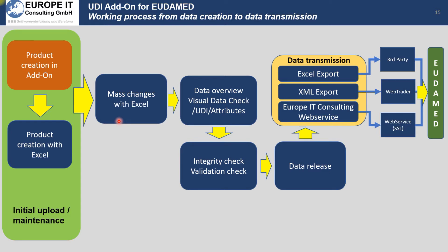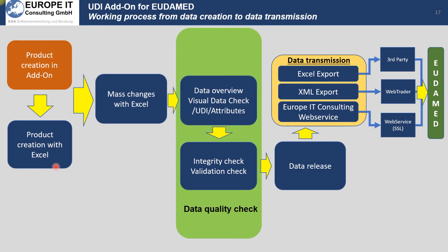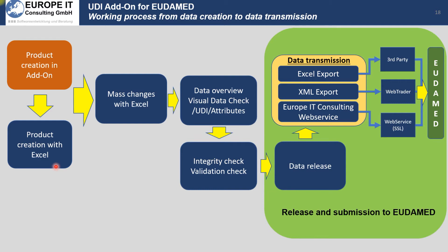The process to maintain your data starts with an initial load on the left side, which I will show in the system. This is a mass upload — product creation with Excel is possible, as well as specific maintenance. Then you switch to mass change, where you can change many devices at one time using Excel. After a visual check to verify data quality, the last step is data submission to the Eudamed database via Excel export, XML export, or our web service for a machine-to-machine connection.